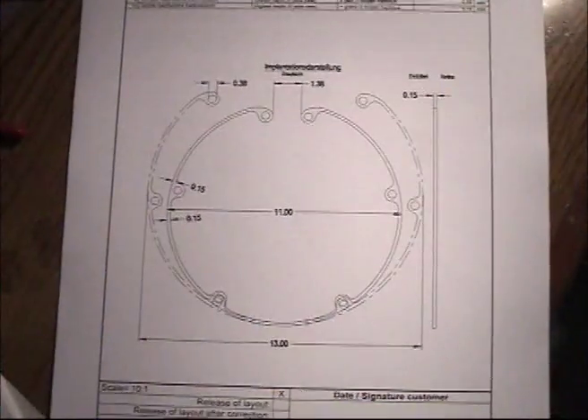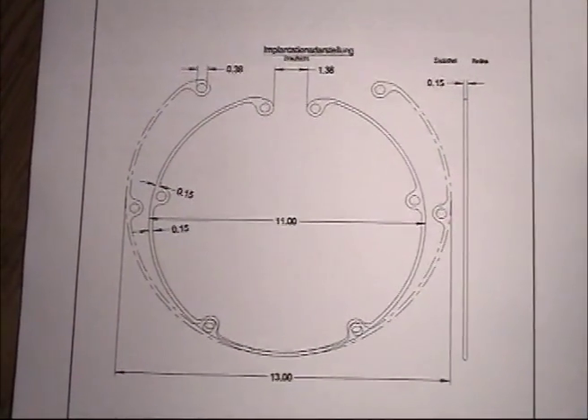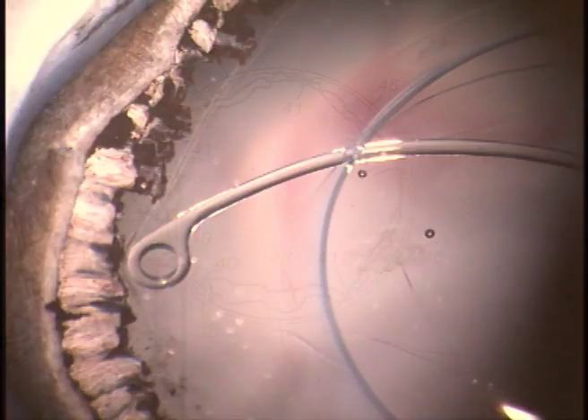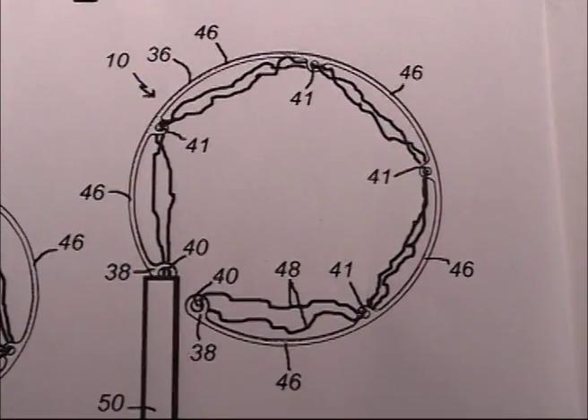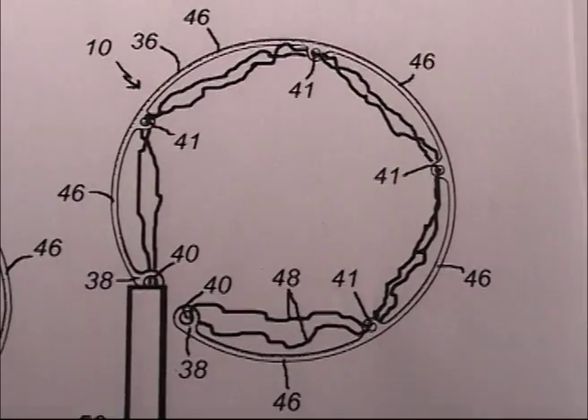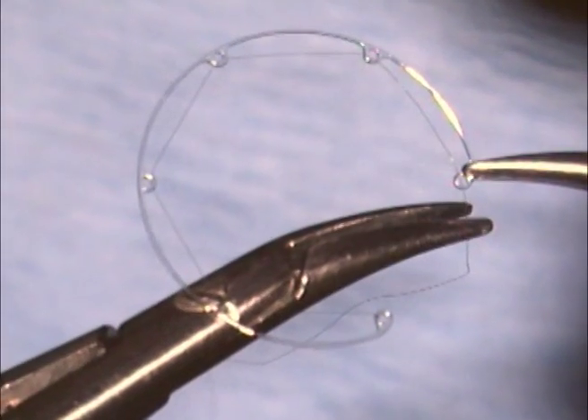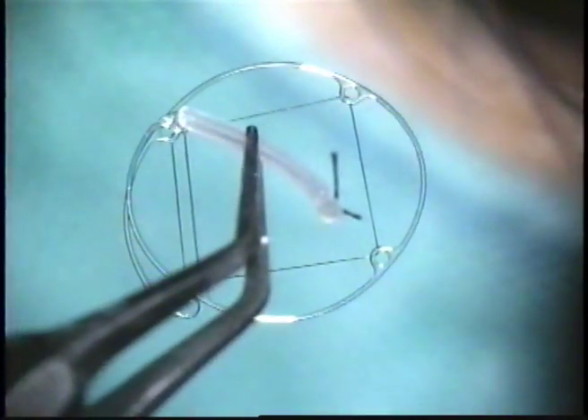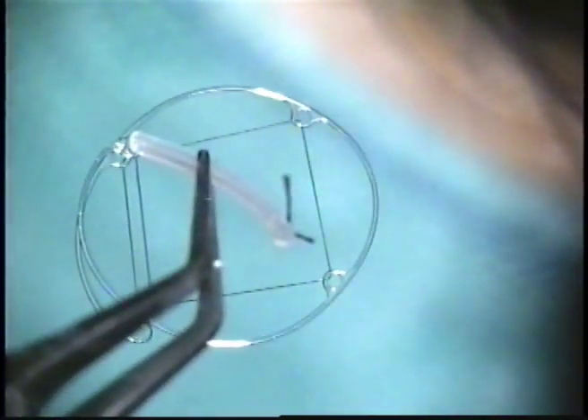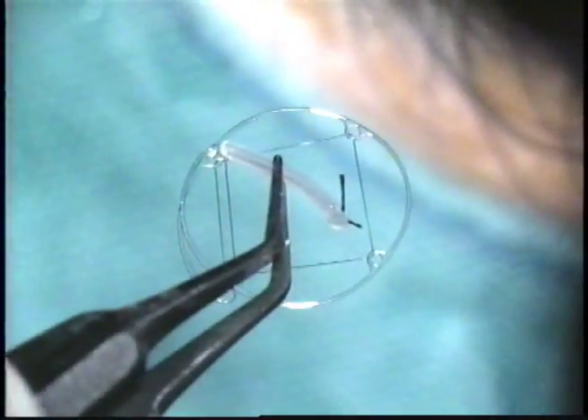With its novel design, we can have a ring that circularly expands within the bag, totally eliminating pinpoint contact zones during insertion. A tensing cord has been passed through each eyelet from one end to the other and back again. Tensing this cord produces an inward bending of the arcs of the ring loop located between the eyelets that serve as cord anchoring points.